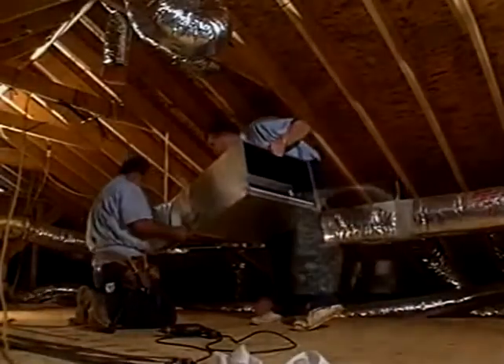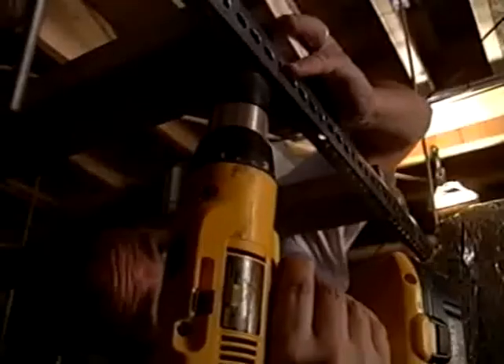Whether you are working in an attic or a crawl space, it is important to make sure the air handler is installed properly. This contractor prefers hanging the unit rather than sitting it on concrete blocks. This not only prevents moisture from corroding the metal exterior, but it can also be a more secure way of setting the equipment. He places 2x4s on the metal frame to elevate the unit. This is to allow more working room for service technicians in the future. He makes the plenum connection by installing a flex connector. This will help absorb vibrations in the system.